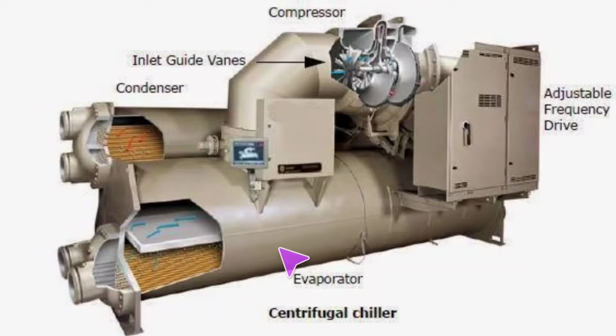And then we just maintain a certain liquid level in the bottom, and all that's calculated in. It's not mechanically metered on these particular machines. And the refrigerant gets pulled back into the compressor from there. You'll see that they do have this little distribution plate. The reason for this plate is so that you've got this big suction volute coming through. You really want to distribute all of the pull across that liquid refrigerant evenly. That refrigerant's going to be below that plate level, and so you're going to have all your liquid refrigerant below that. Anything above that pulling through is going to be all vapor.